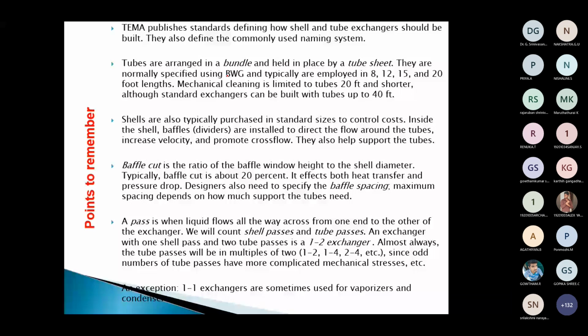Then coming to the baffle cut, it is the ratio of the baffle window height to the shell diameter. The ideal value should be around 20 to 25%. So this plays a vital role in the heat exchanger efficiency.